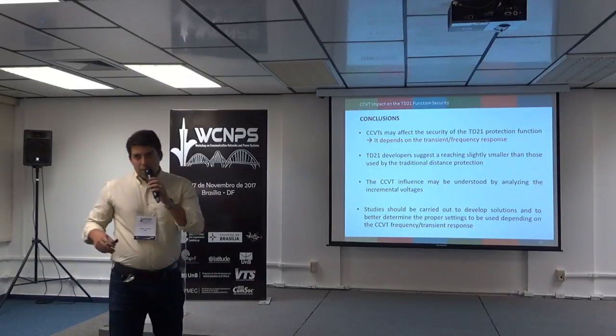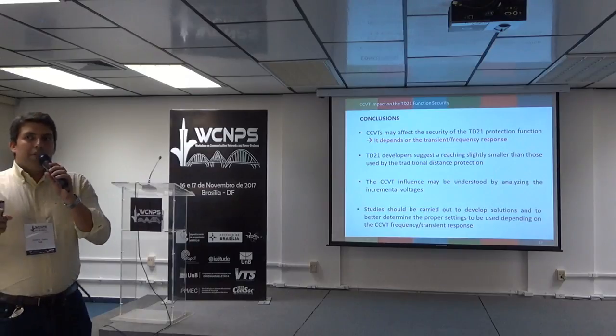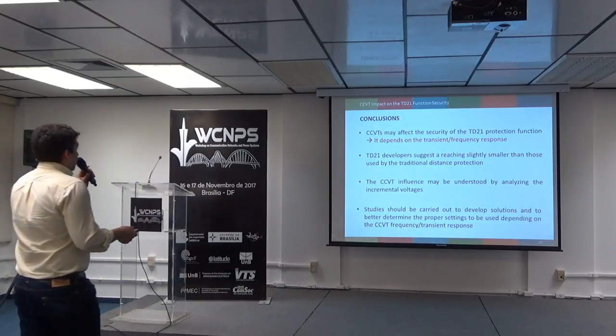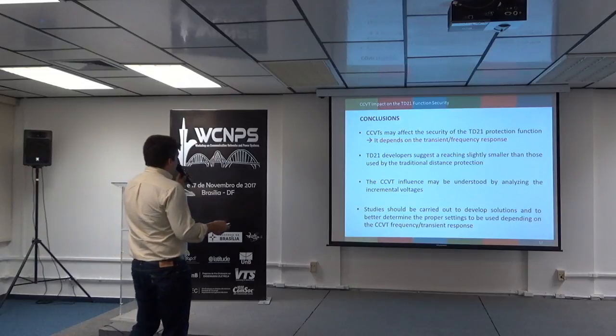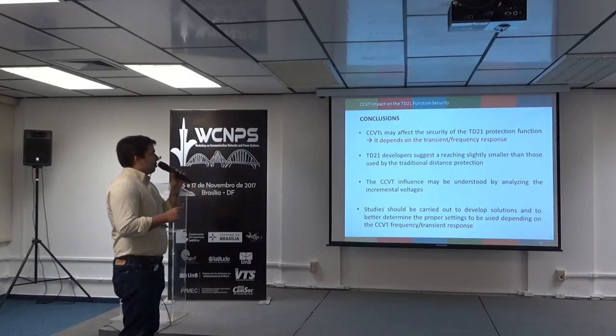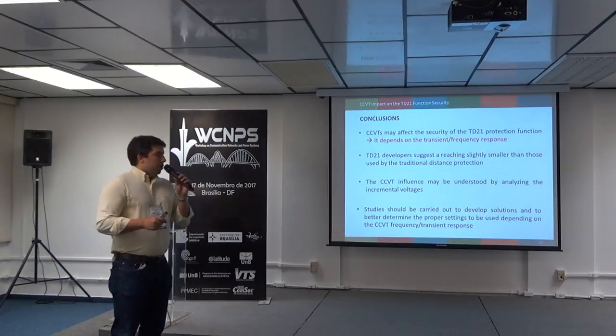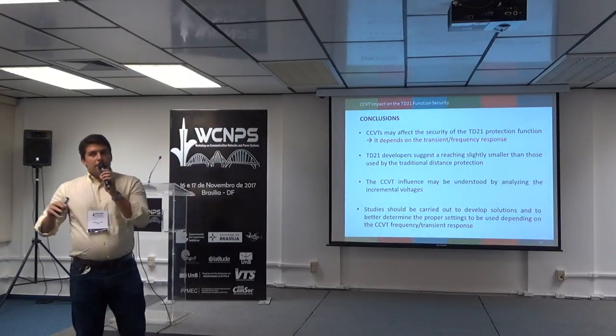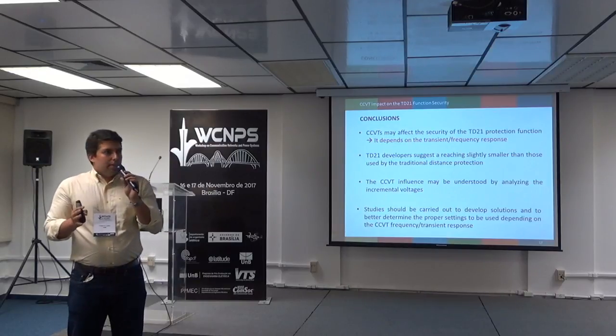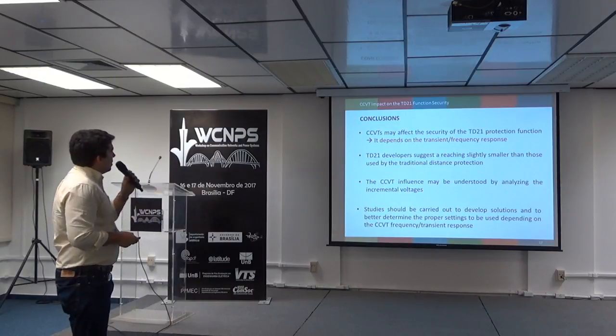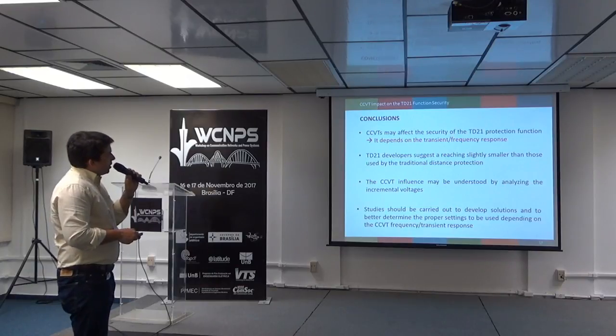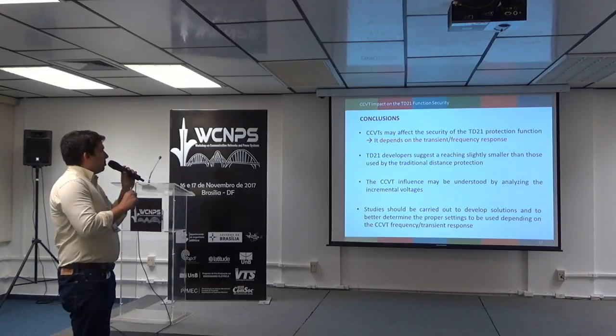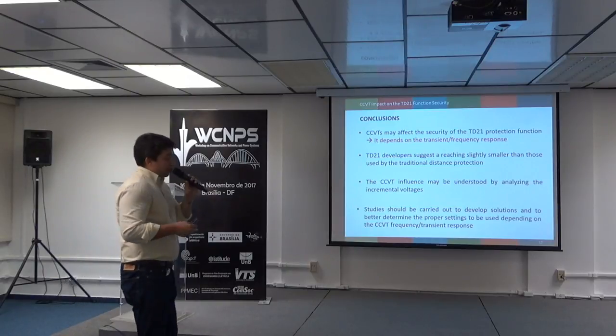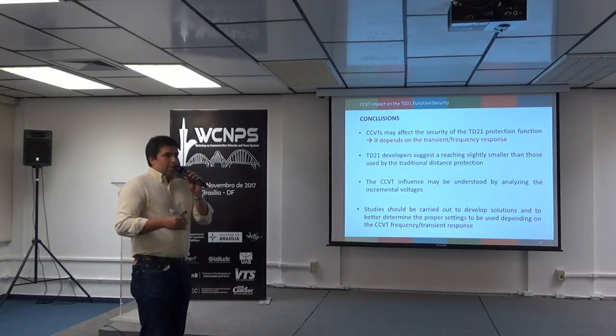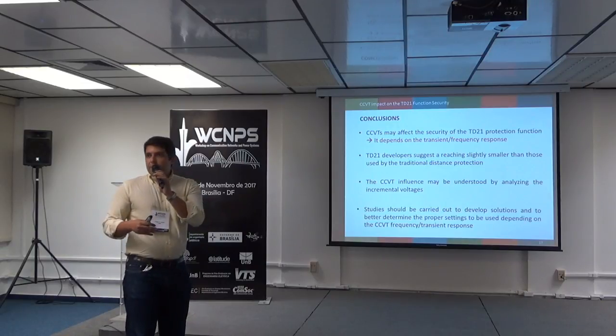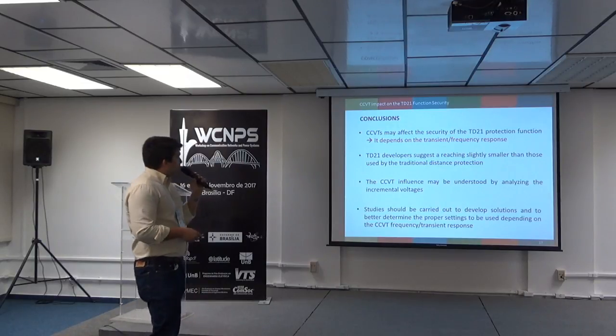So as a conclusion of this part of this research, we can state that the CCVTs may affect the security of the TD21 protection function, but it depends on the transient frequency response of the CCVT. We had problems with this model, but for other models, it may not occur. The TD21 developers suggest a reaching point slightly smaller than those used by traditional distance protection, so we believe that we will have no problem in practice, in real-world fault cases.